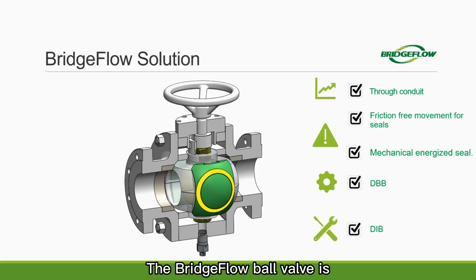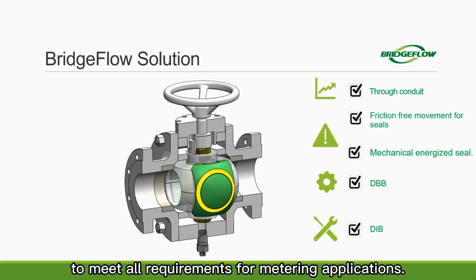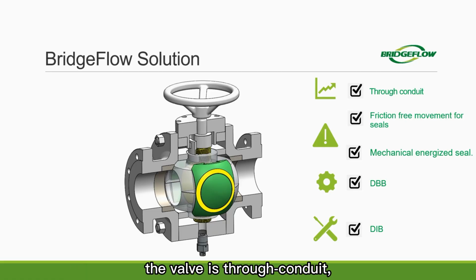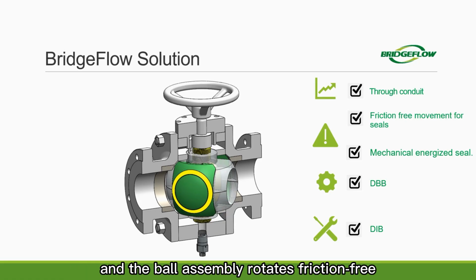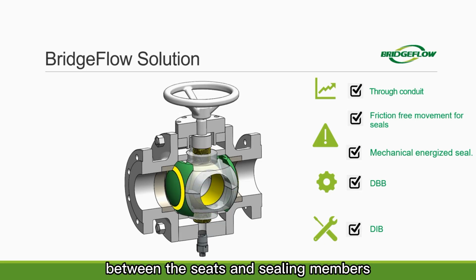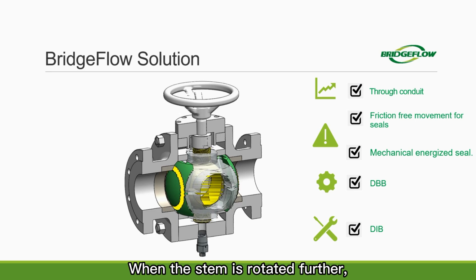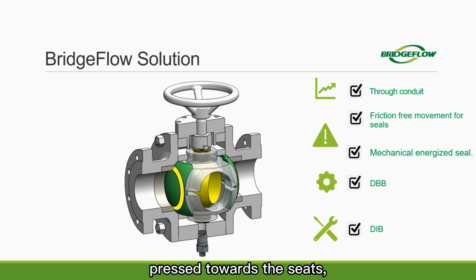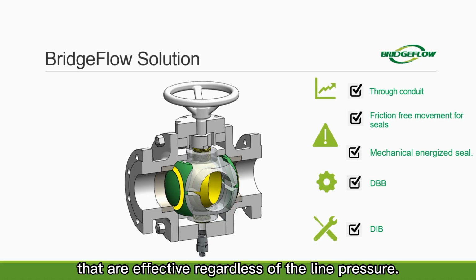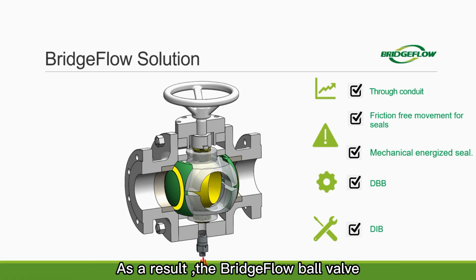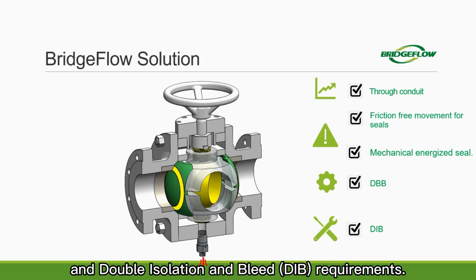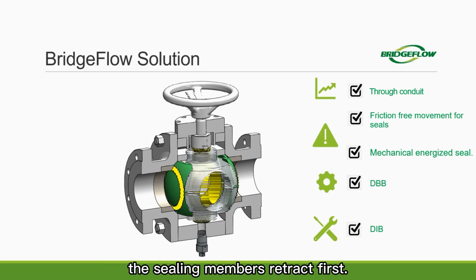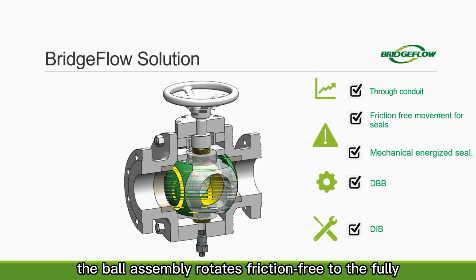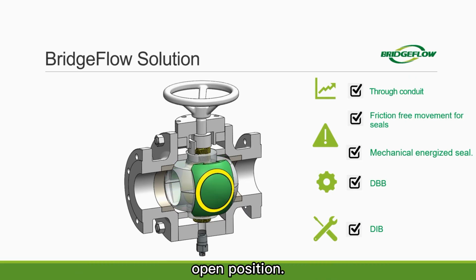The BridgeFlow ball valve is designed specifically to meet all requirements for metering applications. In the open position, the valve is through conduit, and the ball assembly rotates friction-free between the seats and sealing members to close the valve. When the stem is rotated further, the sealing members are mechanically pressed towards the seats, creating two mechanically energized seals that are effective regardless of the line pressure. As a result, the BridgeFlow ball valve meets both double block and bleed DBB, and double isolation and bleed DIB requirements. To open the BridgeFlow ball valve, the sealing members retract first. Then, the ball assembly rotates friction-free to the fully open position.